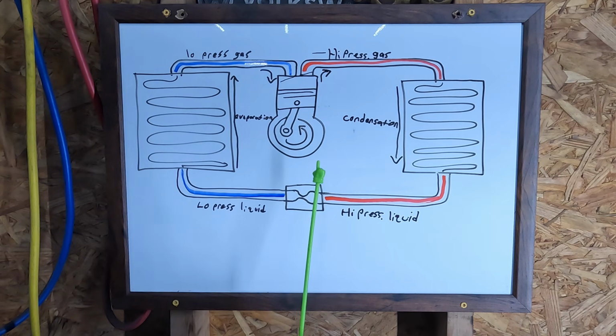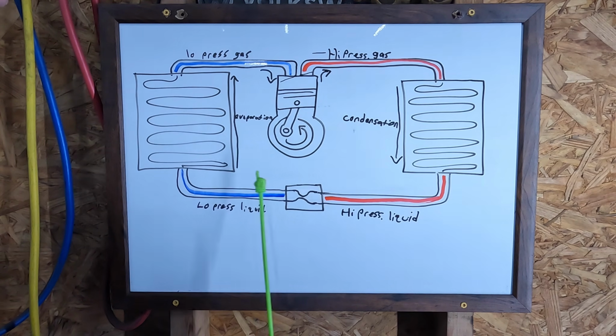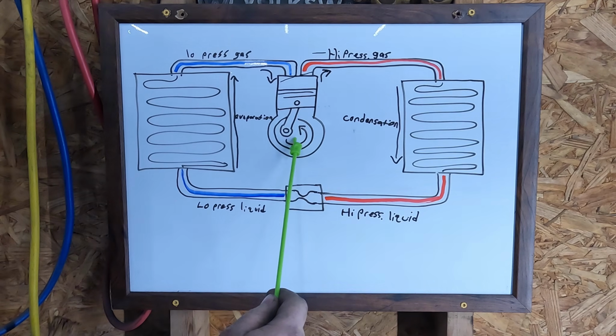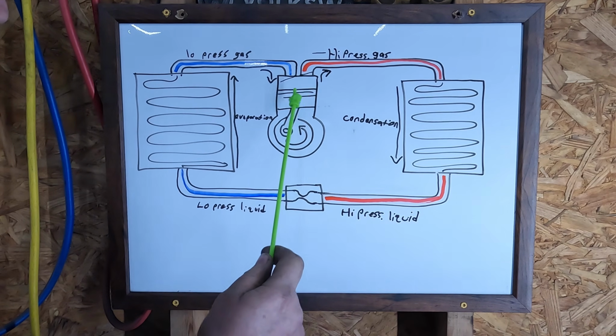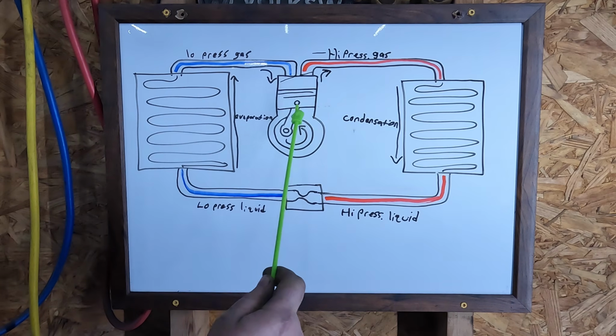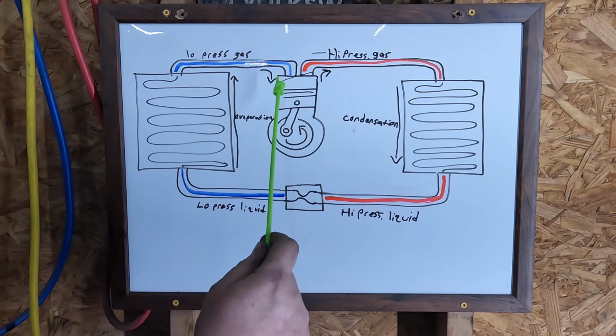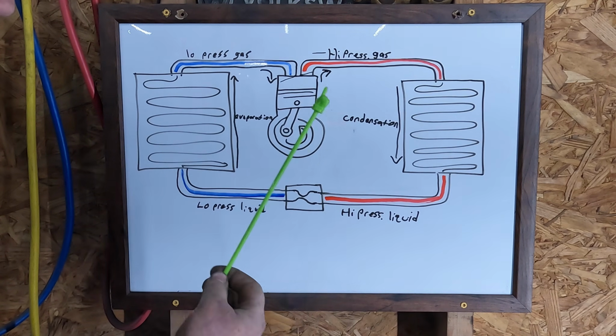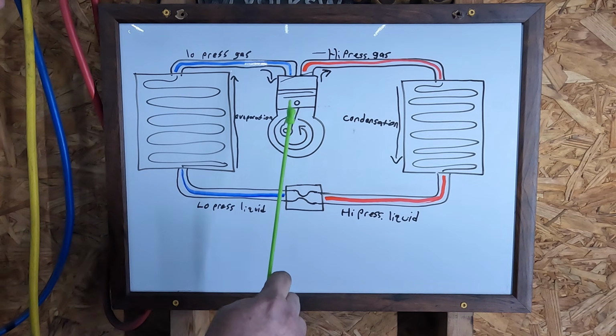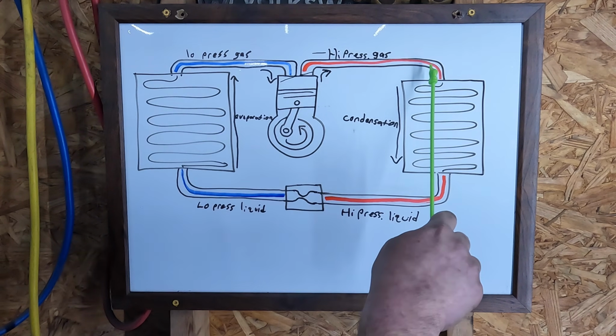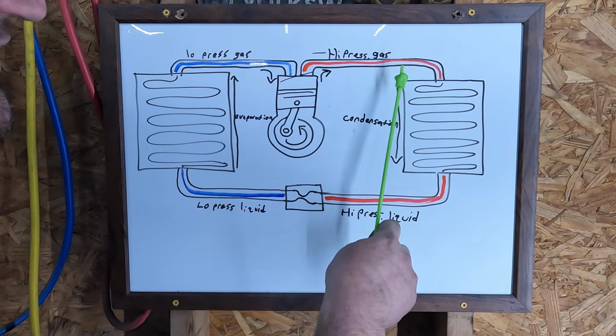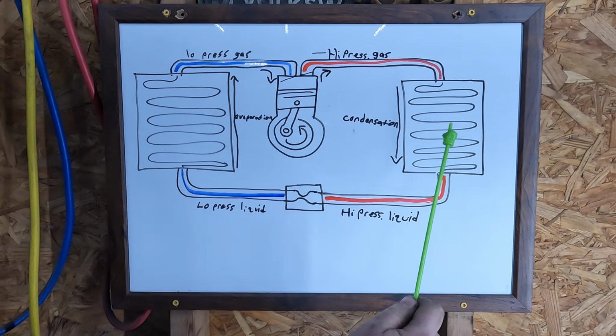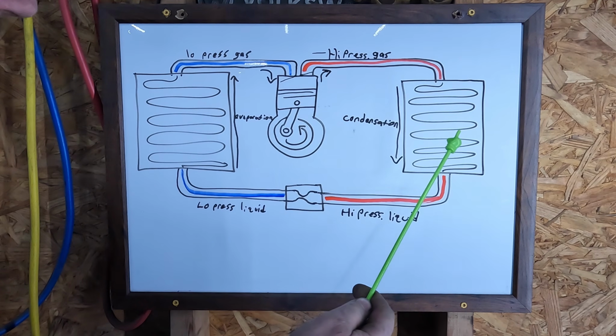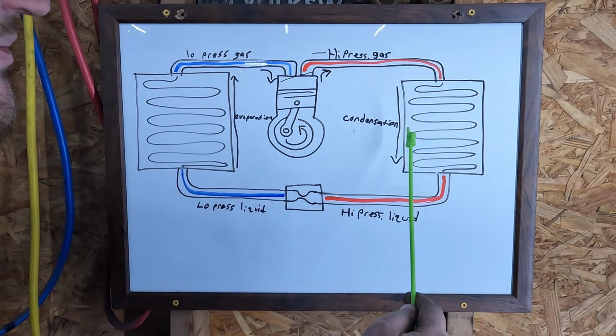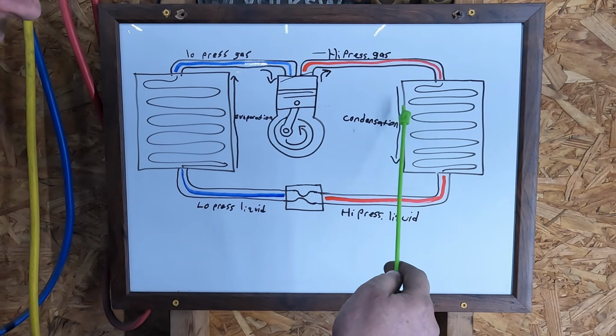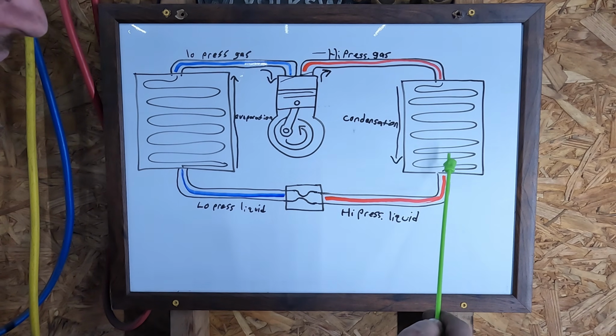So now that I have made a very simplified drawing of an air conditioning system, let me introduce you to the main characters. Here is a compressor, represented as just a simple piston compressor with two check valves at the top. This spins around, makes a low pressure into a high pressure. Over here is the condenser, which takes that high pressure gaseous refrigerant from the compressor and expands its surface area through its many fins and passages and allows it to throw that heat off into ambient air. Of course, air is moving across both these heat exchangers. And as it throws that heat out, it's going to condense back into a liquid.